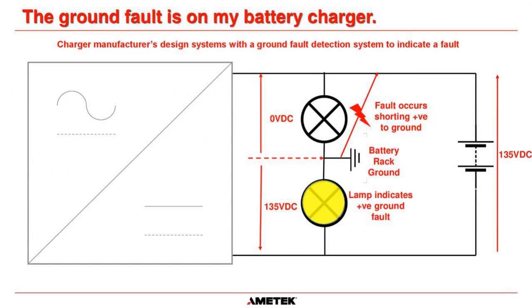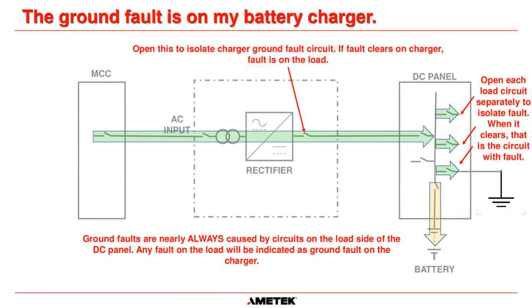So what you have to do is, if you do have a ground fault on the system, I know this is in an ideal world, but the first thing that you should do is this. Open each load circuit separately, and then watch the ground fault detection lamp on your charger. And whichever breaker you open that turns the ground fault light off, that tells you which branch circuit has the fault. Okay?